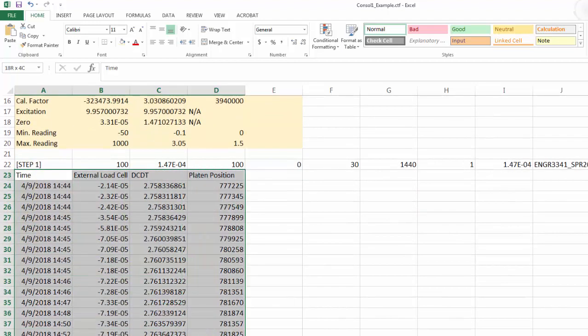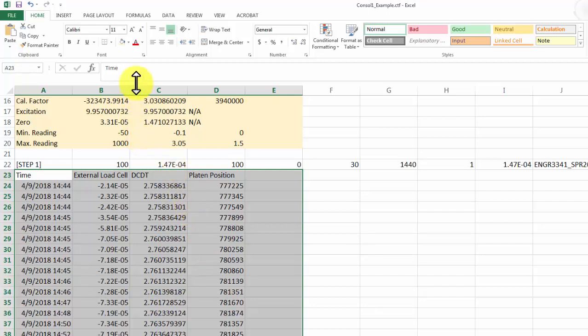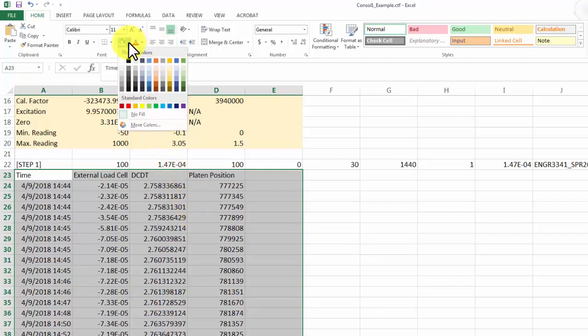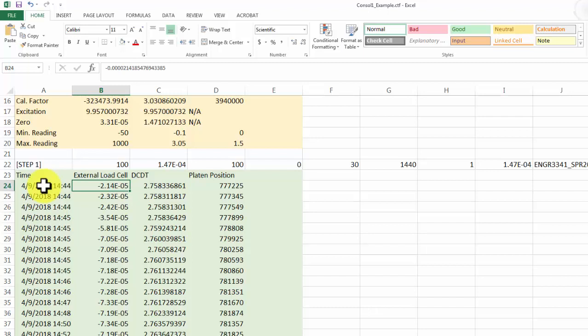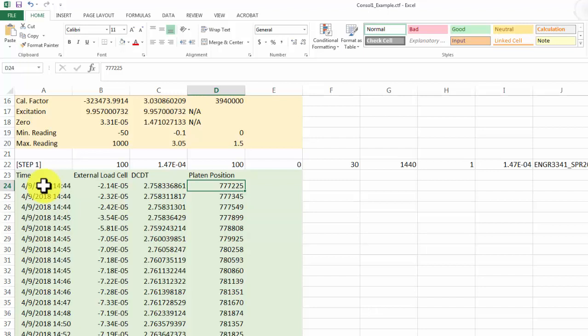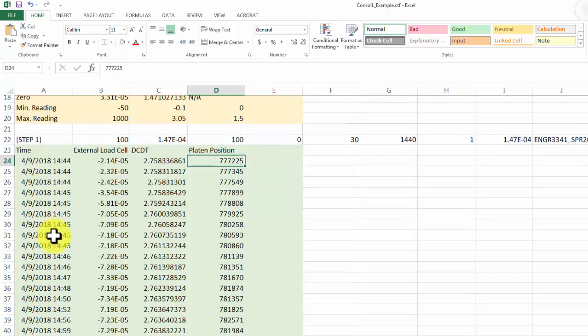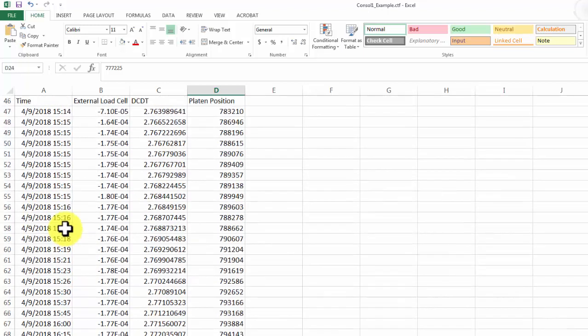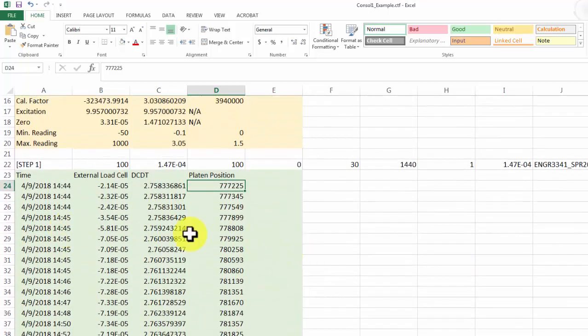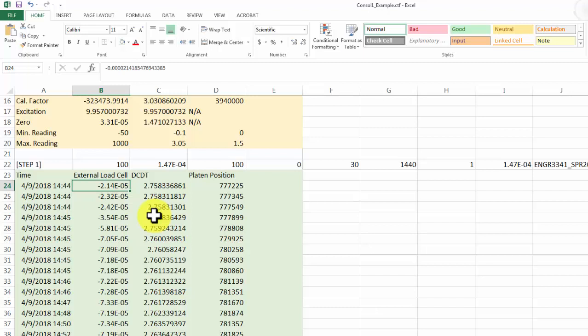Below the sensor section, you'll see a section for each load step that you performed. The first one, highlighted in green, is for step number one. It has readings of the time each reading was taken, the data from the external load cell, the data from the displacement device, and a column labeled platen position — we're going to ignore that one. If you scroll down, you'll see another section for time step two, and another for time step three. For each one we're going to take the raw data and turn it into the information we want.